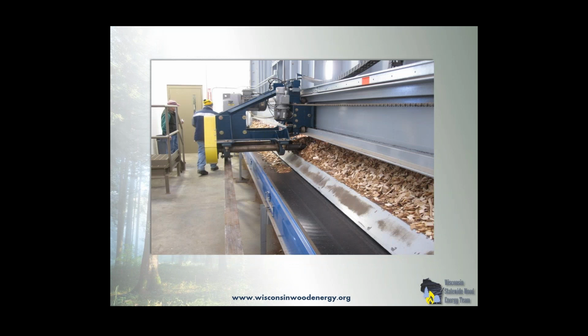This is a picture of the traveling auger. Messerschmitt uses this design. A couple other companies have copied that design. And that auger moves back and forth along the bin on that track and pulls material. In this case, there are 2 augers. They've set it up with 1 or 2 augers. You can see either. They draw the fuel from about an 18-foot length and depth of the bin back onto the traveling belt.